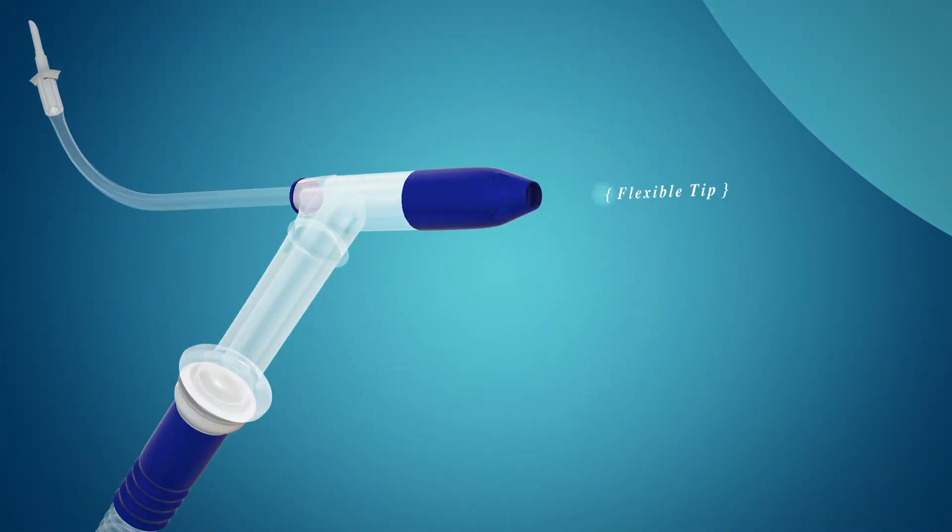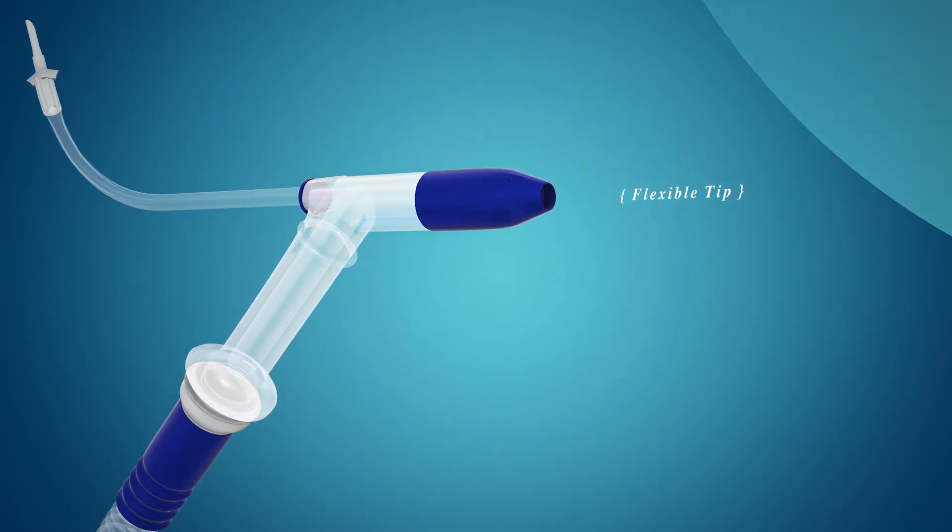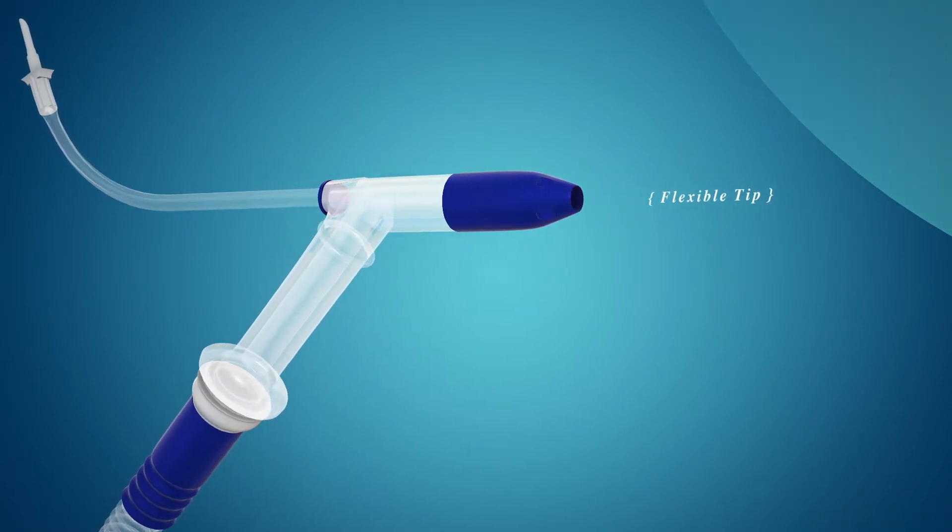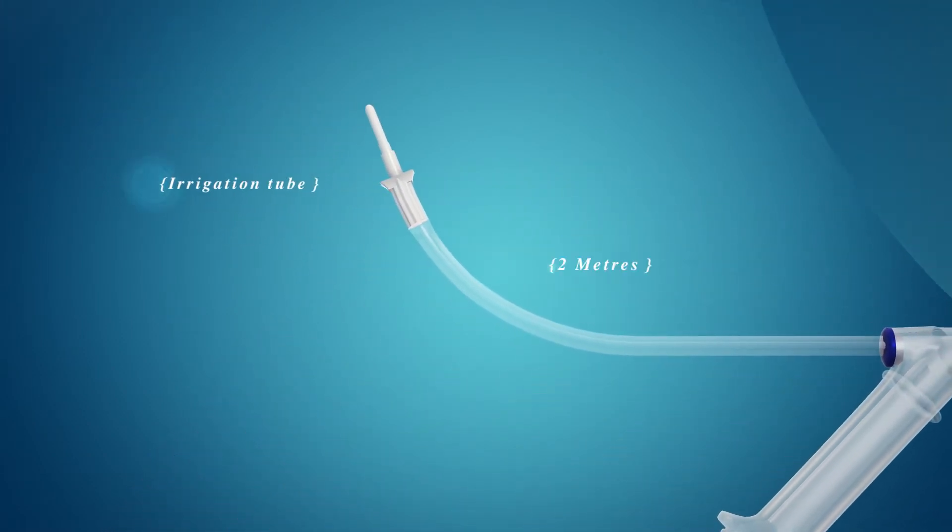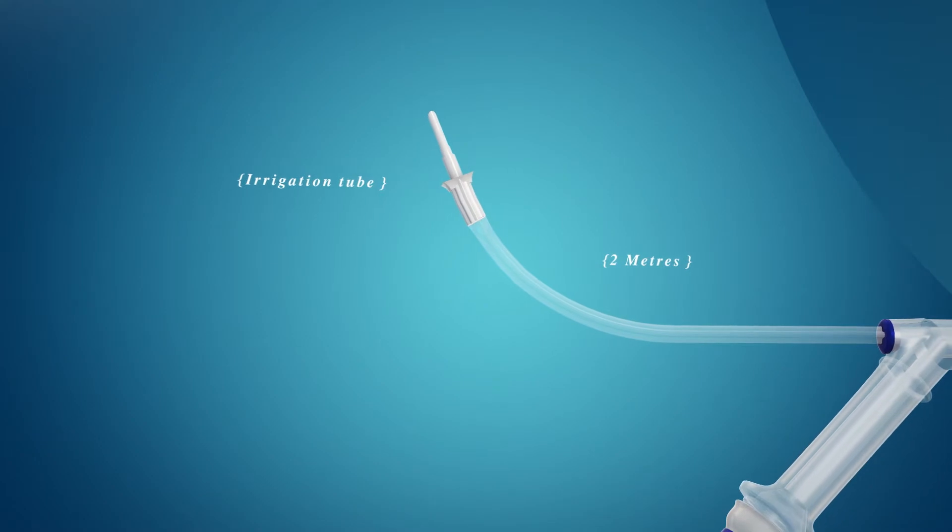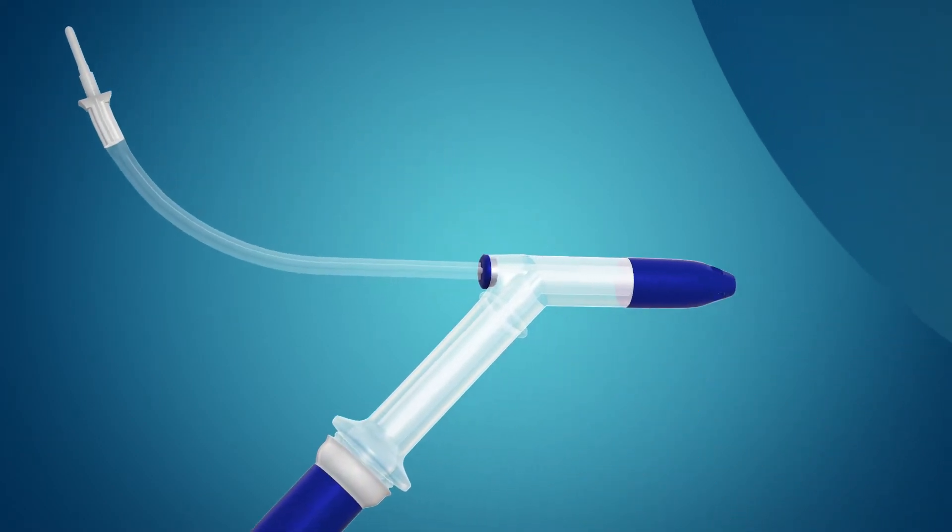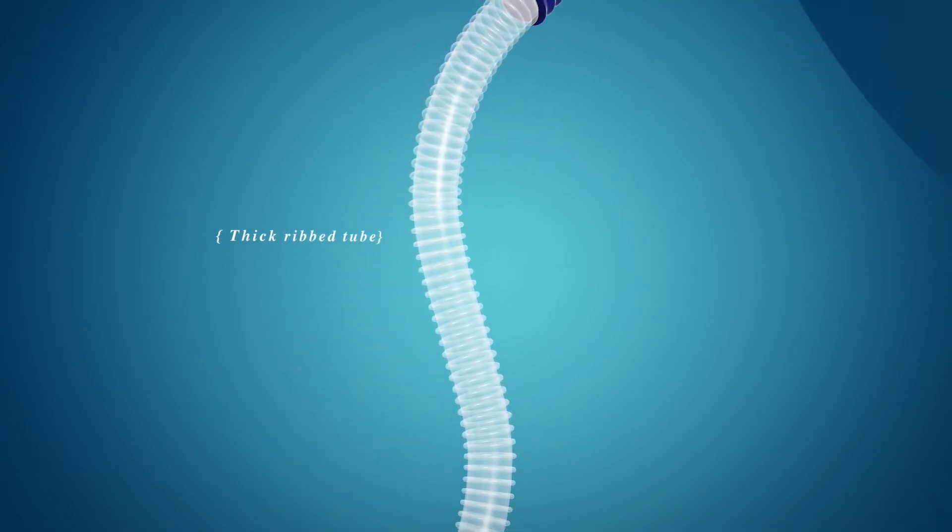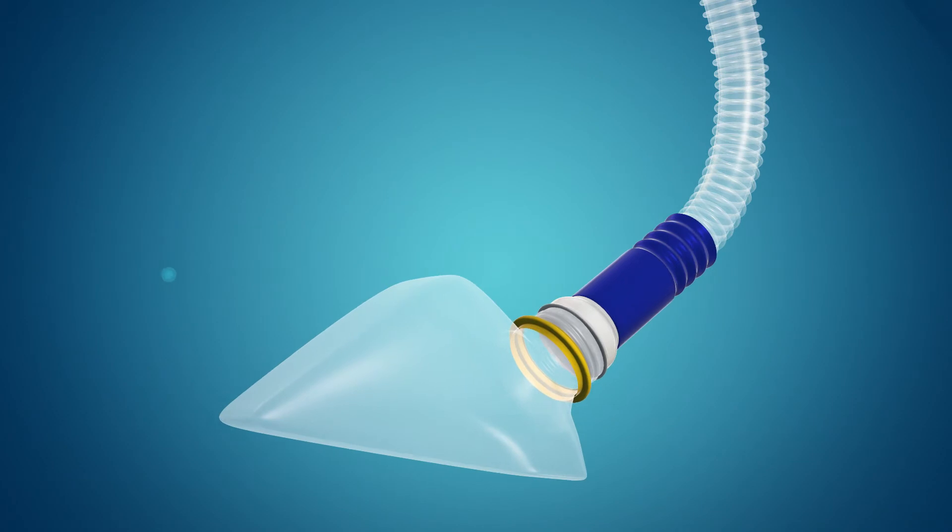By using a flexible tip for atraumatic insertion without an obturator, it is possible to provide a completely closed irrigation system. A high-flow irrigation set, connected directly to a fluid bag, can be passed through the device and positioned at any point in the rectal stump. A wide-bore drainage tube that never blocks leads to a detachable and sealable waste container.